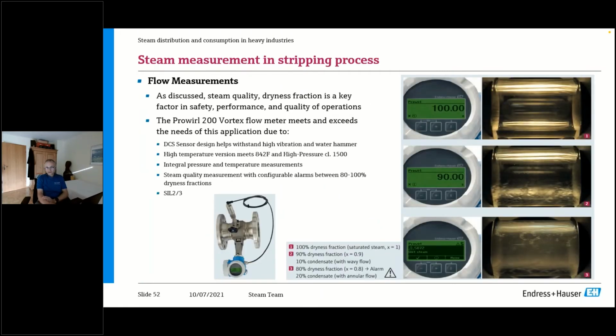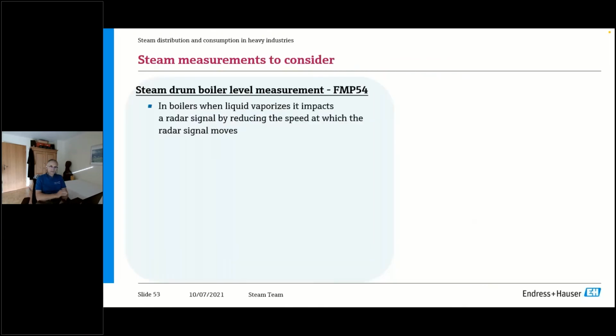And here you can actually see what wet steam looks like. Here we see 100% dry steam. It looks like a gas, so you can't see anything. At 90% dryness fraction in a horizontal line, you get a stream of water forming down here. And at 80%, you get annular flow. And in the middle, by the way, at 80% dryness fraction, you don't see anything. In the middle of the pipeline there is no moisture condensing. It all condenses on the pipe wall, interestingly enough.